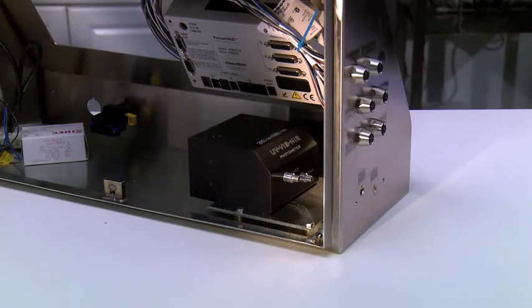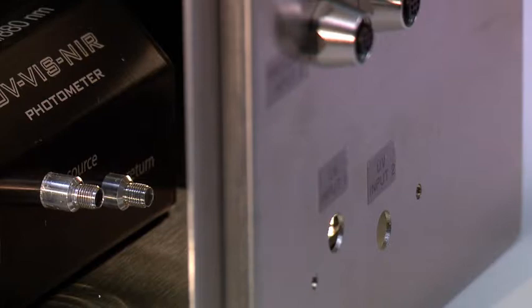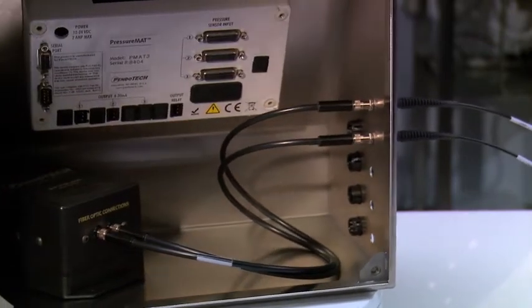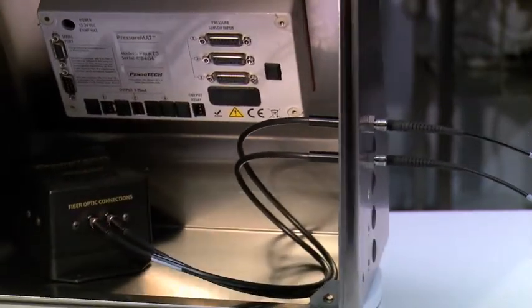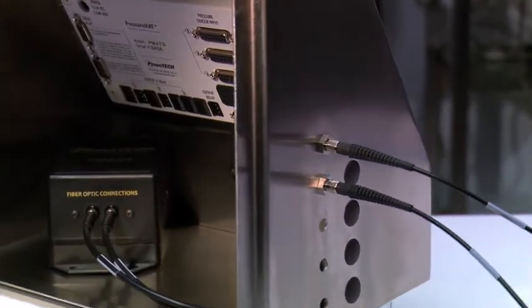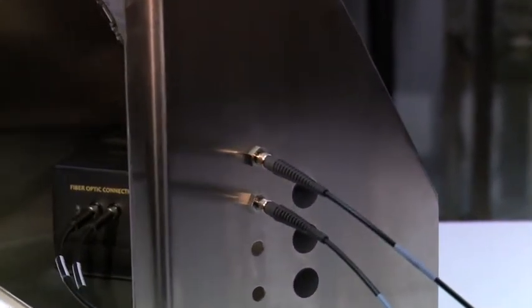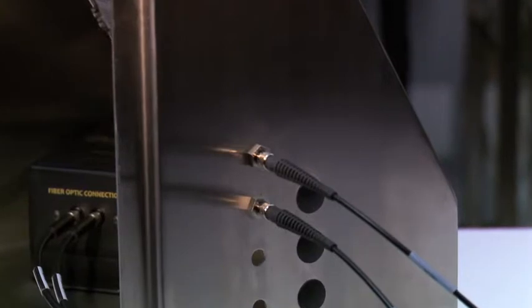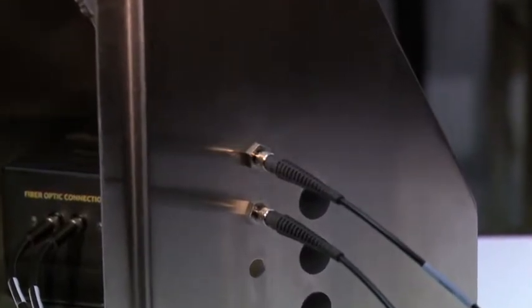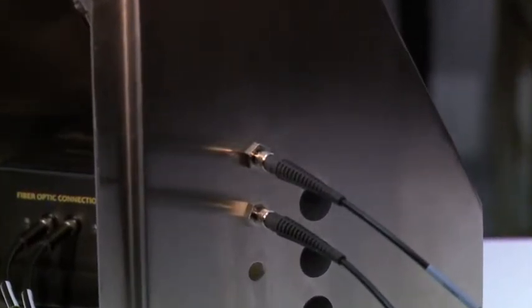The output is typically connected to a process controller such as a PLC or Delta V. There are two options for mounting within an industrial cabinet. One is directly mounting on the inside wall of the cabinet, where the optical ports on the photometer protrude through the cabinet wall. In this case, the photometer has a flangeless base. The second option is mounting the unit somewhere within the cabinet using the base with the flange. In this case, connectors are installed into the wall to facilitate the connection of fiber optic cables on both sides of the connectors. This allows for the passage of light to and from the photometer through the wall.